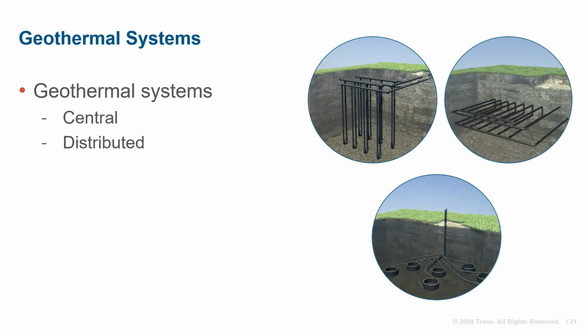Geothermal systems, when designed and operated properly, can be the most efficient system type, but they do require extra effort to ensure a solid design. These systems may be centralized with modest to large equipment in a plant. They may also be distributed with, as an example, relatively small local water source heat pump units connected to a building loop, which is in turn connected to a geothermal well field. In both cases, the geothermal field must be sized to sink and source energy to and from the earth.